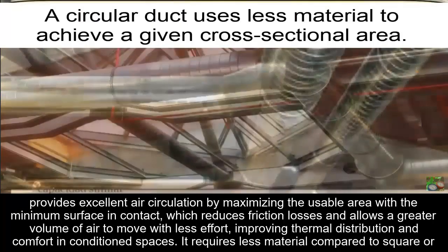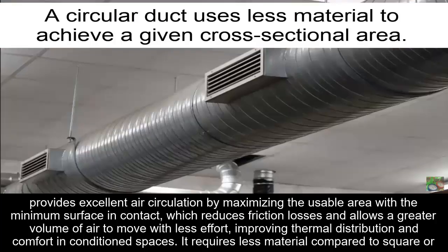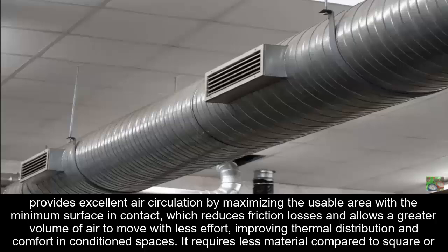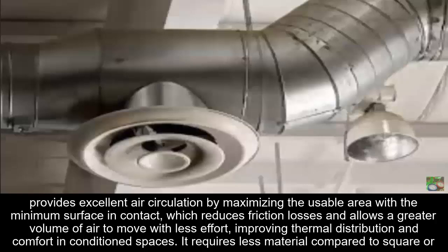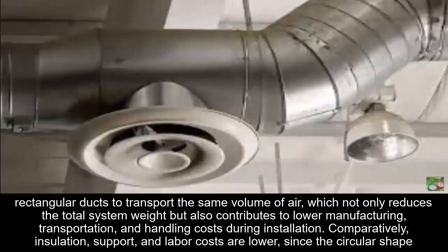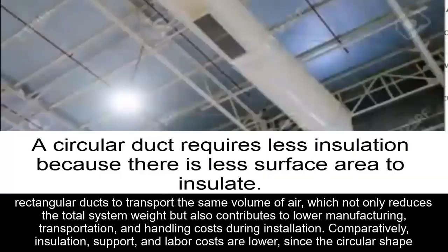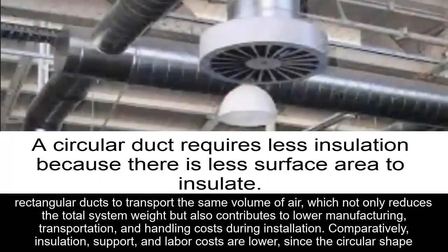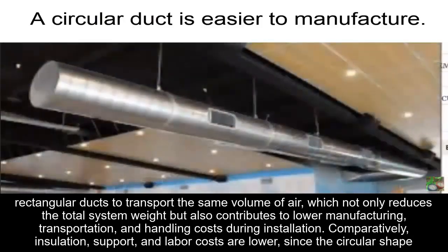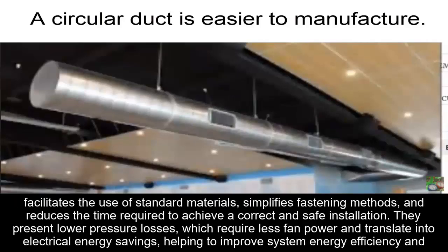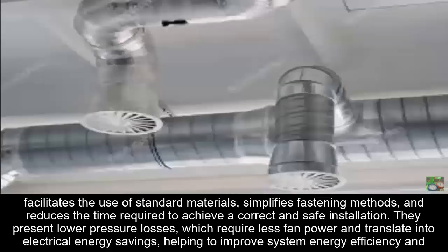It provides excellent air circulation by maximizing the usable area with the minimum surface in contact, which reduces friction losses and allows a greater volume of air to move with less effort, improving thermal distribution and comfort in conditioned spaces. It requires less material compared to square or rectangular ducts to transport the same volume of air, which not only reduces the total system weight, but also contributes to lower manufacturing costs, transportation, and handling during installation. Comparatively, installation, support, and labor costs are lower since the circular shape facilitates the use of standard materials, simplifies fastening methods, and reduces the time required to achieve a correct and safe installation.